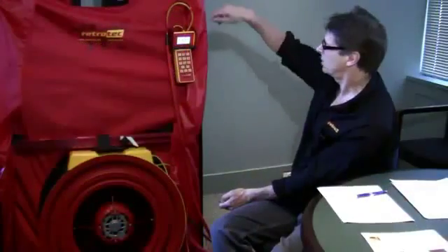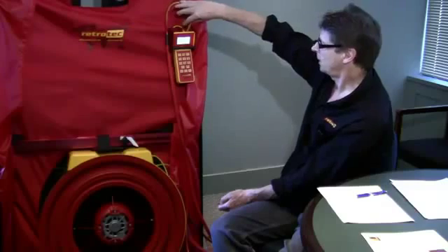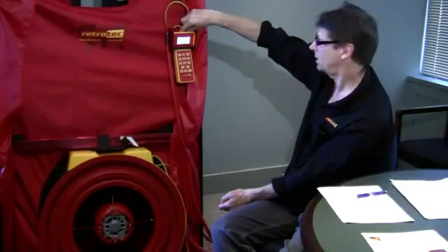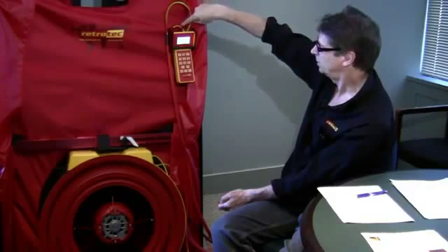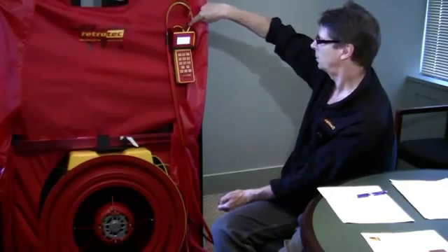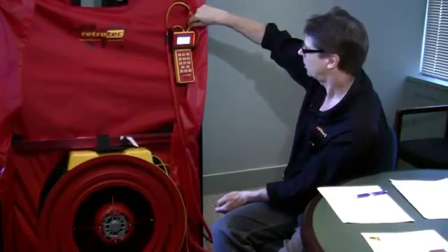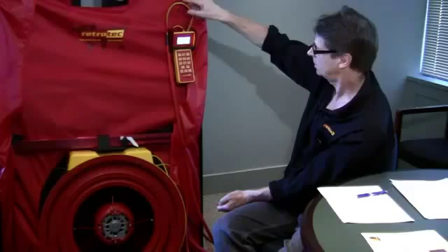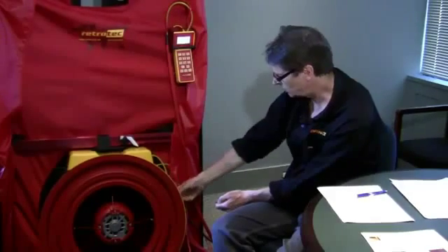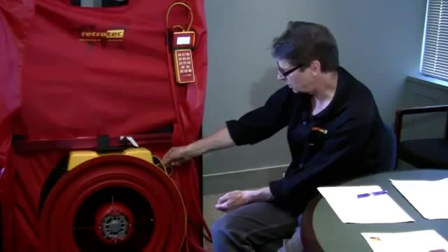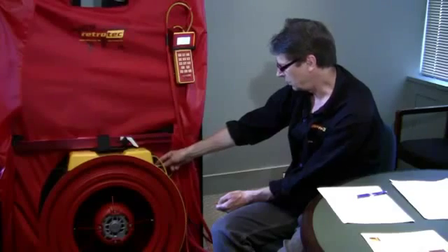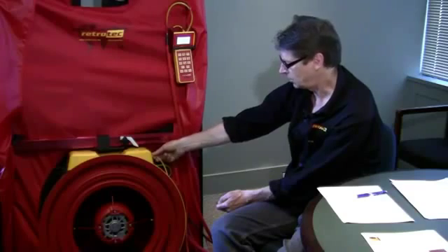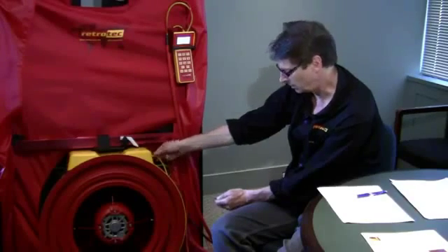Our gauge setup consists of the red tube and yellow tube being connected to the red and yellow ports on the gauge in this particular case for building pressure and for fan pressure, and a yellow Ethernet cable which comes out, which is a control cable. This comes down over towards the fan, and the yellow connector goes into the fan onto the reference B port, and the Ethernet cable, which is the controlling cable, goes into the fan.